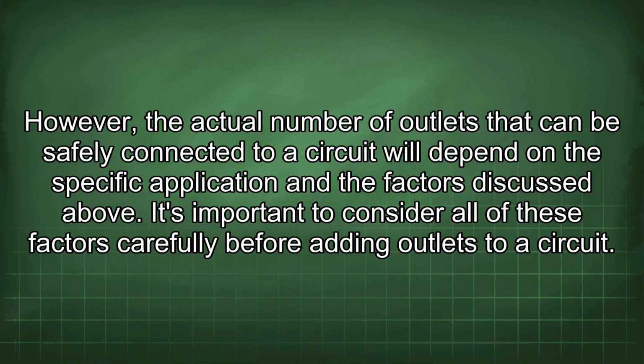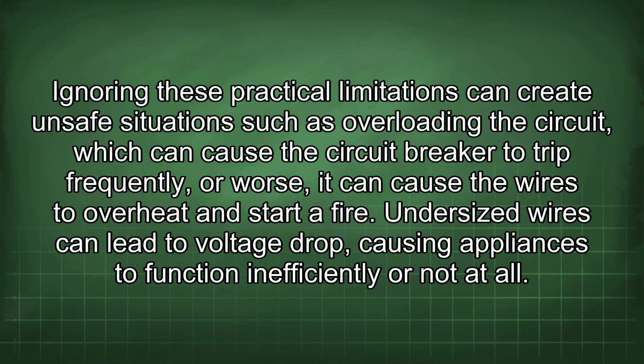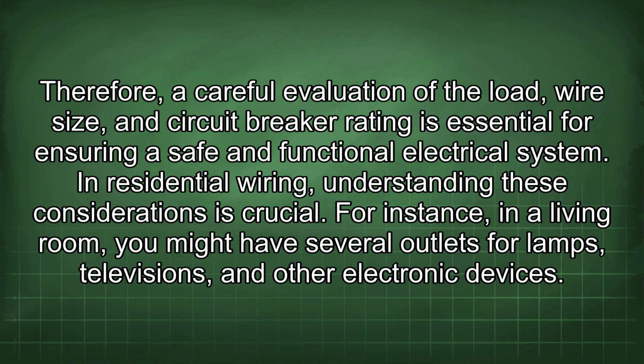It's important to consider all of these factors carefully before adding outlets to a circuit. Ignoring these practical limitations can create unsafe situations such as overloading the circuit, which can cause the circuit breaker to trip frequently, or worse, it can cause the wires to overheat and start a fire. Undersized wires can lead to voltage drop, causing appliances to function inefficiently or not at all. Therefore, a careful evaluation of the load, wire size, and circuit breaker rating is essential for ensuring a safe and functional electrical system. In residential wiring, understanding these considerations is crucial.